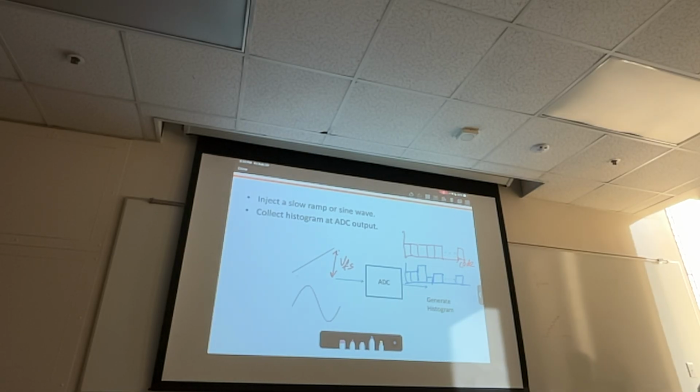So all in all, it all comes down to the signal that you generated. Even though you thought that should be a ramp, it won't be a perfect ramp, right? The slope can be changing. You cannot keep the same constant slope. Remember, here, it's very important for you to keep the same slope. You agree? You ramp up, you better keep a constant slope. If you start to vary the slope, then your histogram starts to change, even if you have a perfect ADC. You see that?